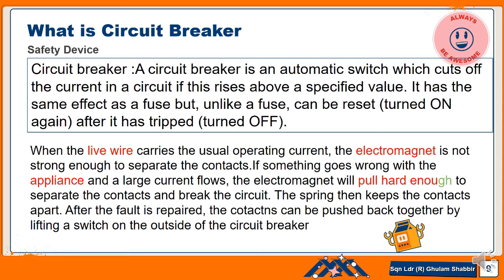So a circuit breaker is an automatic switch which cuts off the current in a circuit if the current rises above a specific value. For example, if the circuit breaker is to be used for a 3 ampere electrical appliance, then the rating of the circuit breaker may be 3.1 to 3.5 ampere. So if the current exceeds 3.5 ampere, this circuit breaker will be tripped. It is turned off automatically. So when the problem is rectified, then we can turn it on again.